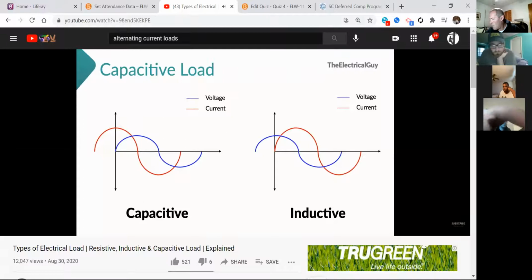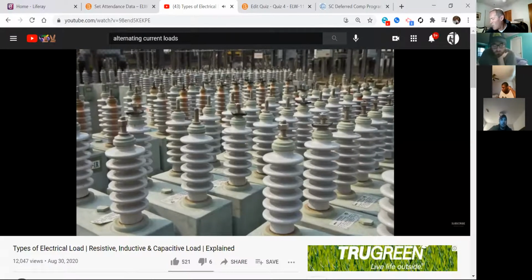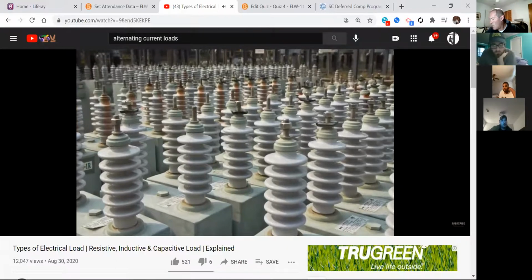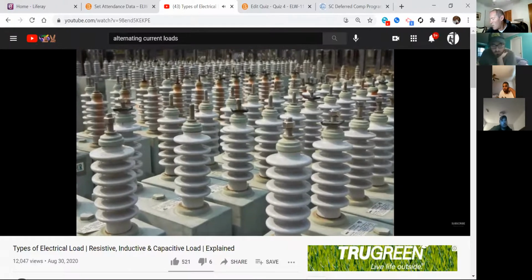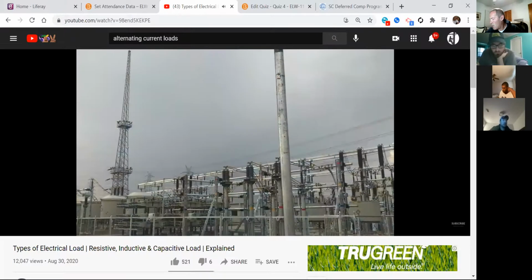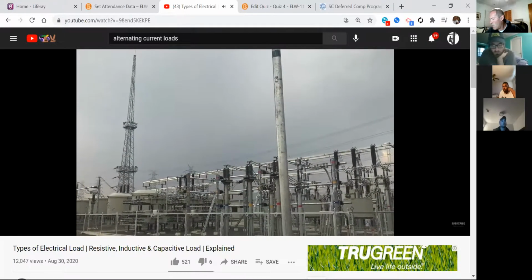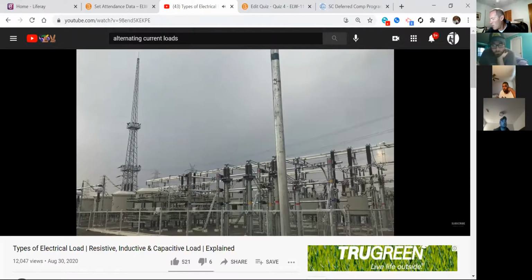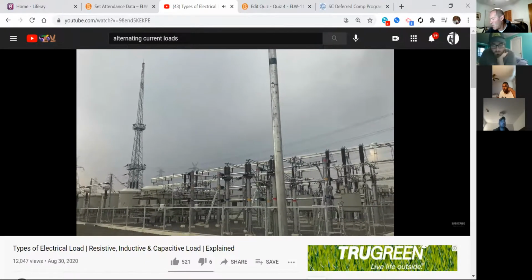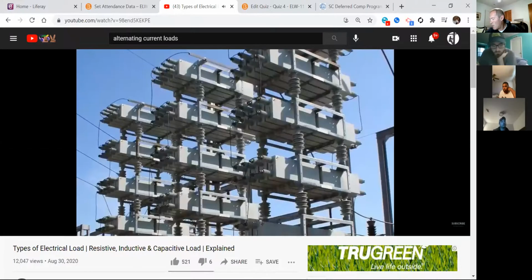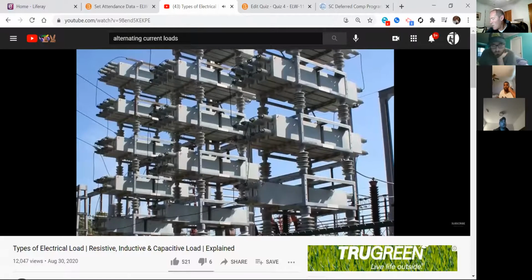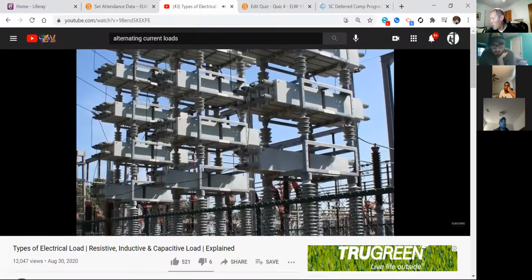Now let's talk about the misconception I mentioned at the beginning of this video. Capacitive loads do not exist in standalone format. Capacitor banks are installed to improve the power factor of a load or system. Their job is to supply reactive power. Therefore, we cannot call capacitor banks a capacitive load, because a load is something that absorbs power. I've seen many places on the internet calling capacitor banks a capacitive load, but I think since a capacitor bank supplies reactive power, it cannot be classified as a capacitive load.